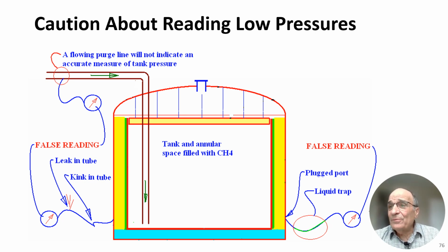If you're reading a tank pressure, you want to be referenced to an inside and outside pressure. You don't want to be inside a building where the building itself is pressurized and you're reading that gauge inside the building, unless it's a transmitted pressure. But let's say it's cold outside and the operator is reading a gauge and he goes into a building and lets the hose be extended to where he's reading. Well, that building may be pressurized, either negatively or positively, and that can affect your reading. These are things you don't typically think about, but what I'm trying to encourage is thinking of all the things that can happen.